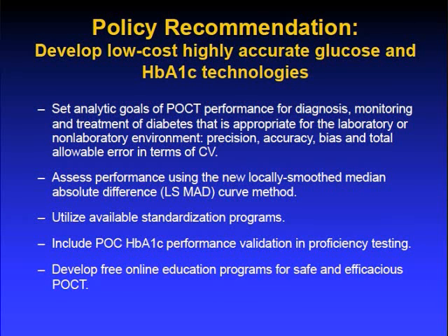The first recommendation is to develop low-cost, highly accurate glucose and hemoglobin A1c technologies. Set analytical goals for point-of-care technology performance for diagnosis, monitoring, and treatment of diabetes that are appropriate for the laboratory or non-laboratory environment. Include precision, accuracy, bias, and total allowable error in terms of CV.